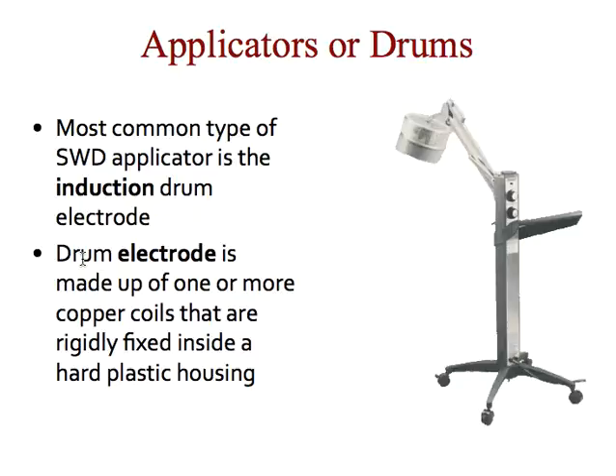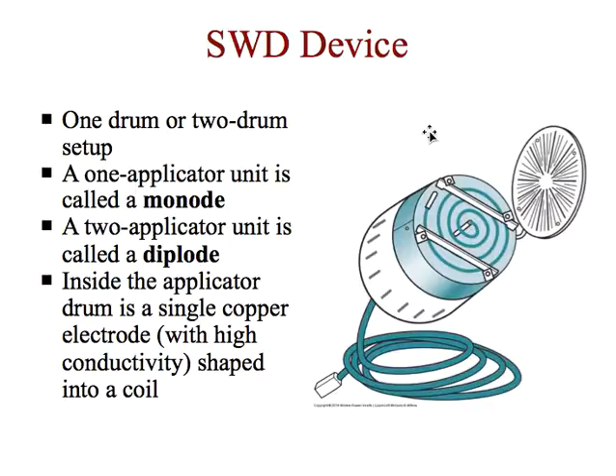The shortwave diathermy device has an applicator or drum, and the most common type is called an induction drum electrode. One or more copper coils are in the housing, rigidly fixed. If there's just one drum being used, it's called a monode. If two drums are used for the treatment, it's called a diplode.